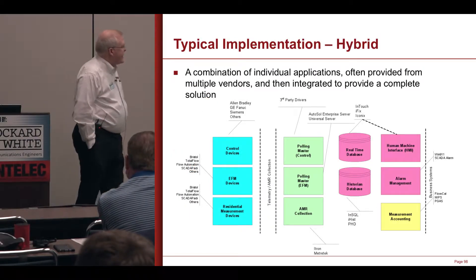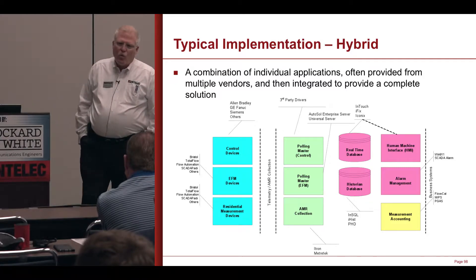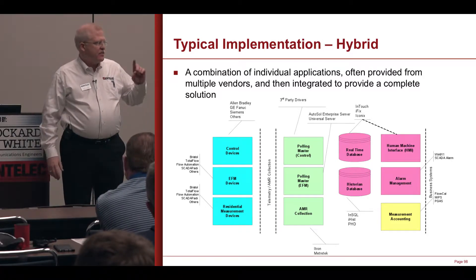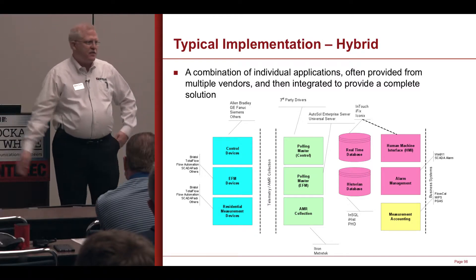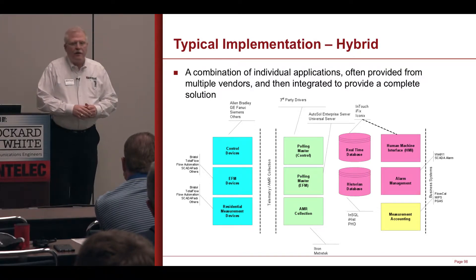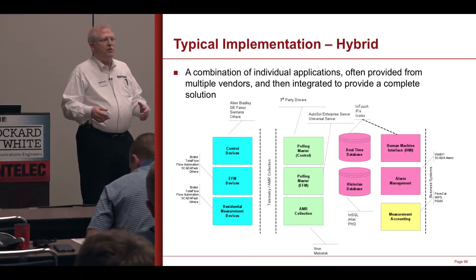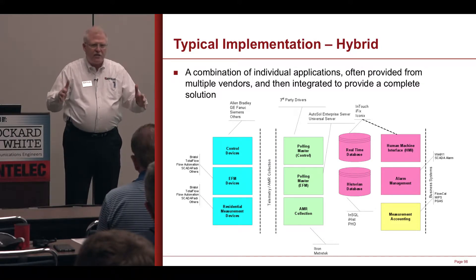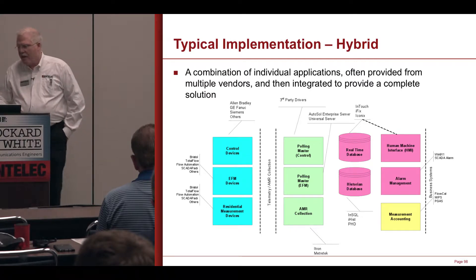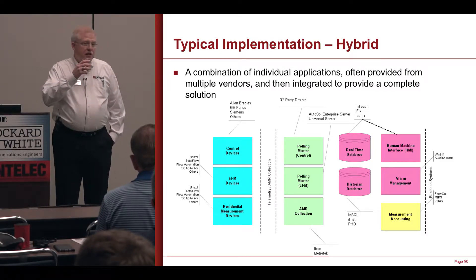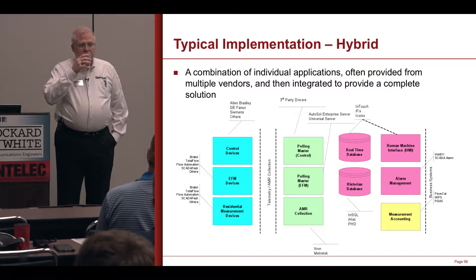There are two basic kinds of SCADA implementation. One is what I'd call a hybrid — you get this vendor's HMI package, this vendor's historian, this vendor's polling package, and so forth. At some level, all SCADA systems are a hybrid. Other products — Cygnet and Oasis are good examples — are monolithic, meaning all the feature sets are available in one software package. The trade-off: hybrids let you get best-of-breed for all the various things you need, but you can have integration challenges. Monoliths might not be best-of-breed for all the different feature sets you're looking for.